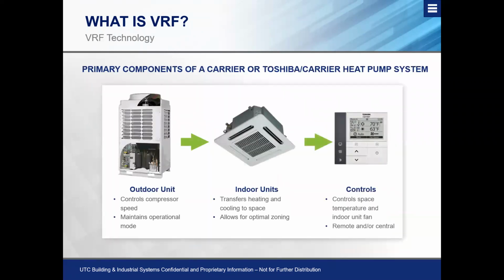So, primary components of our Carrier or our Toshiba Carrier. Now in this particular case, this is going to be a primary example of a heat pump style system. So this is all heat and all cool. So of course we have our outdoor unit, which is going to house our compressor, our electrical section, outdoor coil, and outdoor fan motor. We have our interconnecting refrigeration pipe that's going to connect to multiple or single indoor units. Now, in this case, we have our cassette, but we have the ability to facilitate high wall units, ducted units, vertical air handling units, floor console units. There's a wide variety of options that we have to meet various spaces.